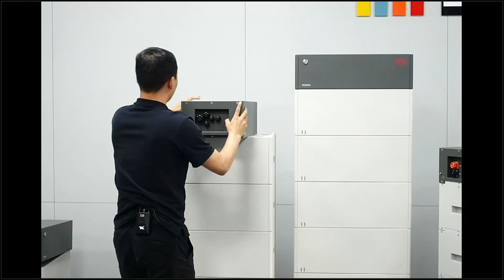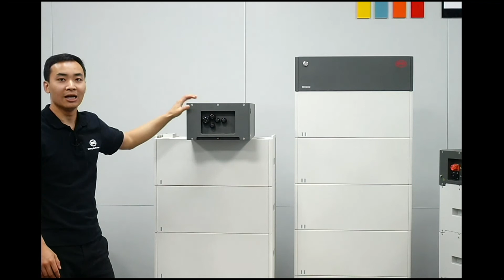For the BCU, it has 5 gaskets here, 2 for the power cables and 3 for communication cables. That's the only place you need to do the wiring job. To do it, first you have to remove the 5 screws to remove the side plate of the BCU, and then you go inside the BCU. Let's have a detailed look here.